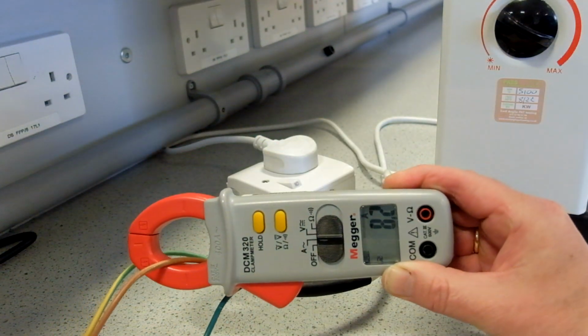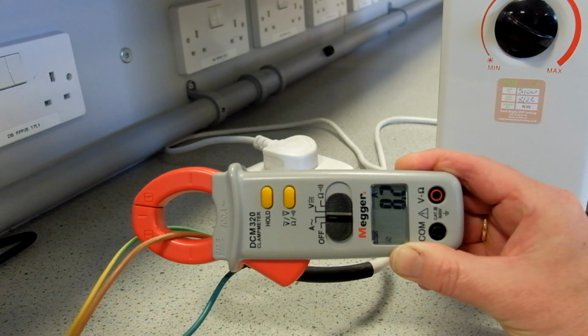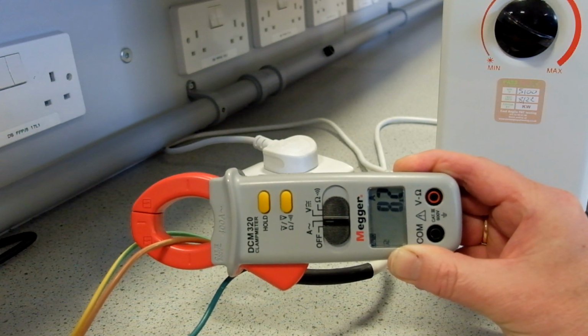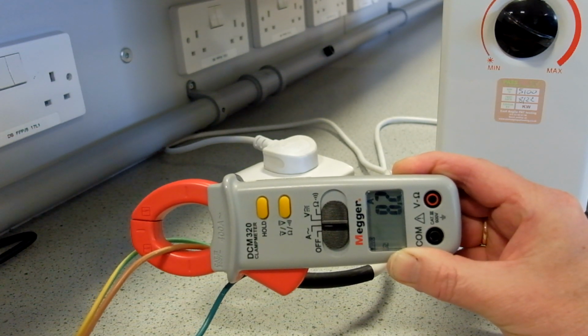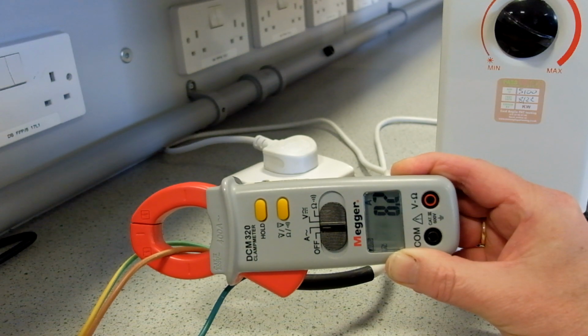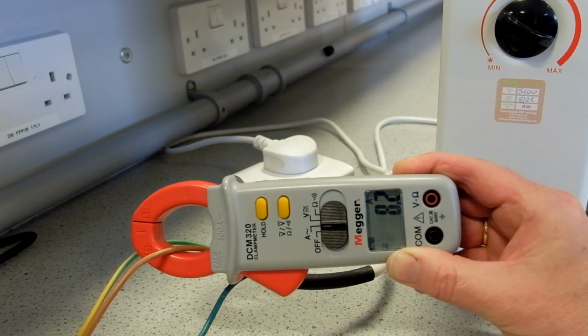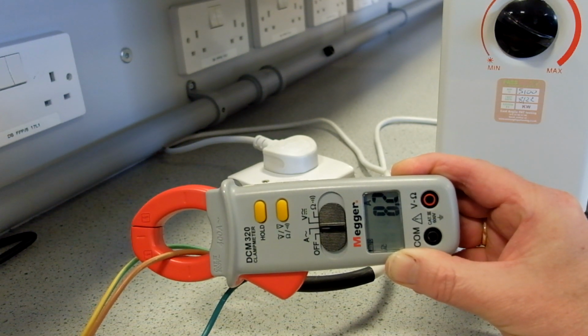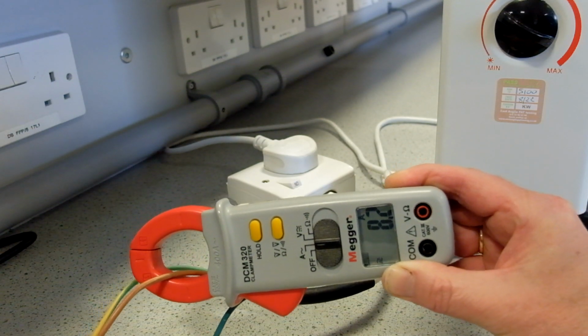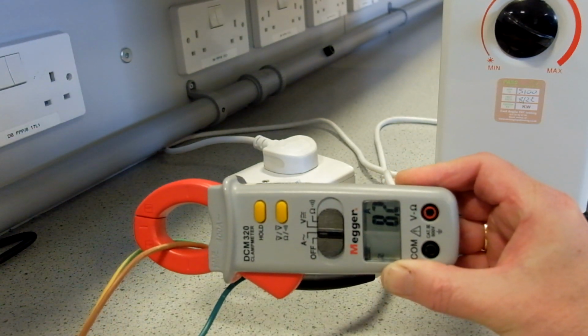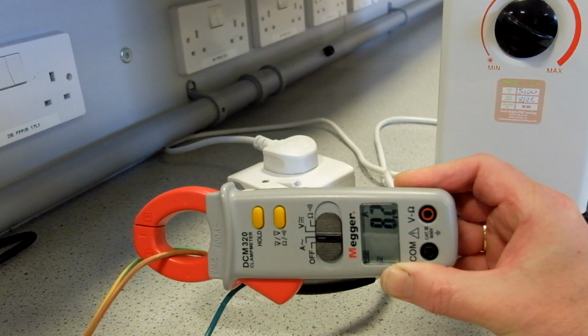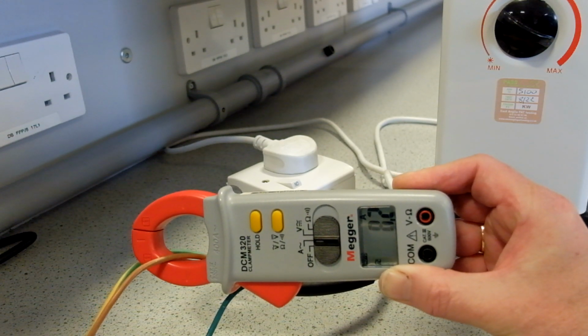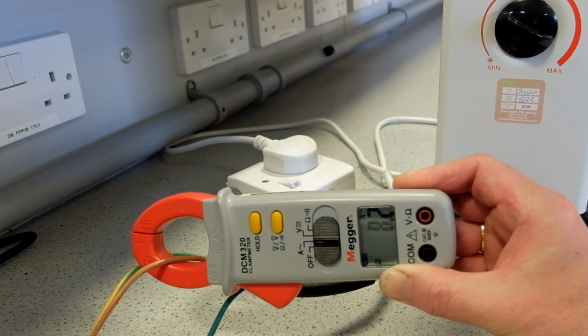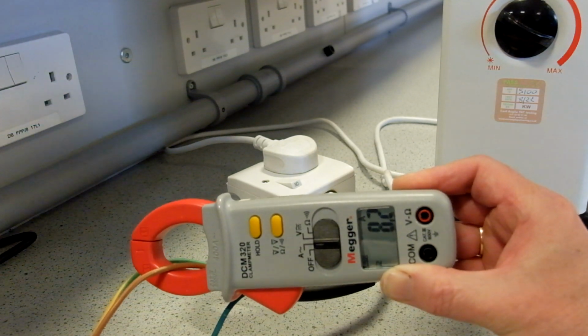The core provides a single turn, and wrapped round that is a coil of multiple turns, which allows a current transformer to operate where you're picking up the magnetic field, and the instrument, the clamp meter, is translating that magnetic field into a current reading. Thank you for watching.